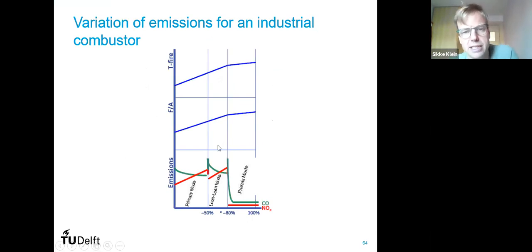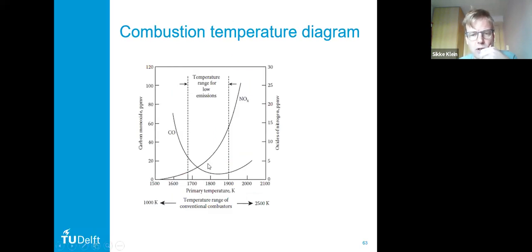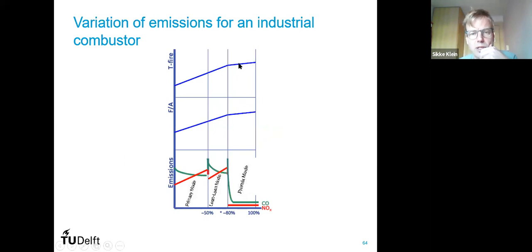And it's something like I said here. So for example, this is typically for a GE engine, the situation where you control the air mass flow by the inlet guide vanes. And actually you control the turbine inlet temperature to the combustor. You can imagine if you control the turbine inlet temperature, the only equipment between the turbine and the combustor is the transition piece, so it has very little impact on the temperature. So in this case you also control the flame temperature. Only where you have this high flame temperature and you are in this region for the NOx can you apply premixed combustion.